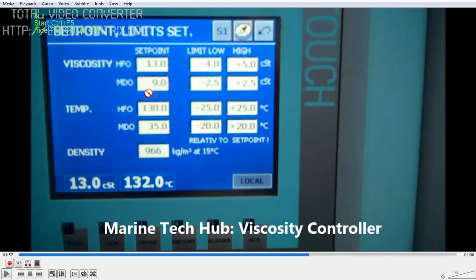For MDO here, put 9 normally. We should maintain the LSMGO viscosity at more than 2 centistroke. So if it is not, then use the chiller to cool the oil to bring the viscosity above 2 centistroke. Normally you maintain 4 to 5, which will be very good.